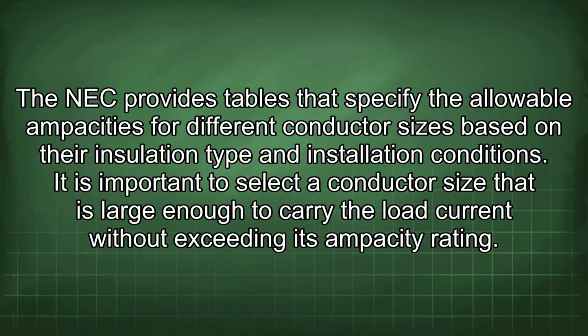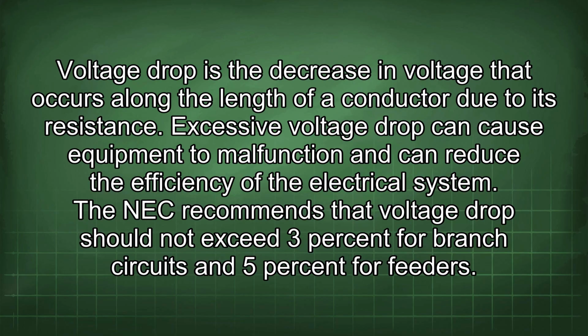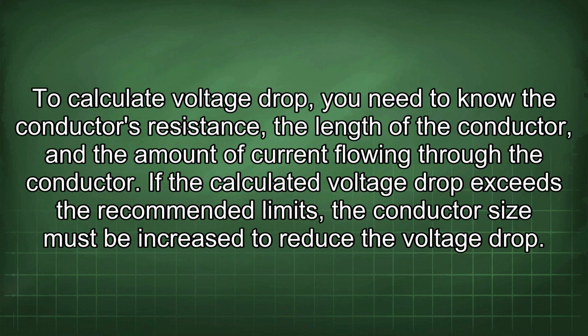The NEC provides tables that specify the allowable ampacities for different conductor sizes based on their insulation type and installation conditions. It is important to select a conductor size that is large enough to carry the load current without exceeding its ampacity rating. Voltage drop is the decrease in voltage that occurs along the length of a conductor due to its resistance. Excessive voltage drop can cause equipment to malfunction and can reduce the efficiency of the electrical system. The NEC recommends that voltage drop should not exceed 3% for branch circuits and 5% for feeders. To calculate voltage drop, you need to know the conductor's resistance, the length of the conductor, and the amount of current flowing through the conductor. If the calculated voltage drop exceeds the recommended limits, the conductor size must be increased to reduce the voltage drop.